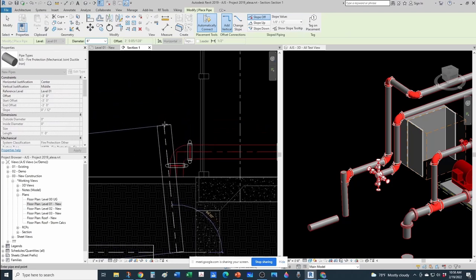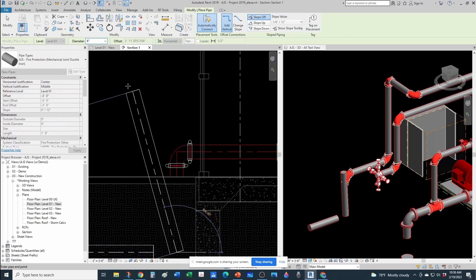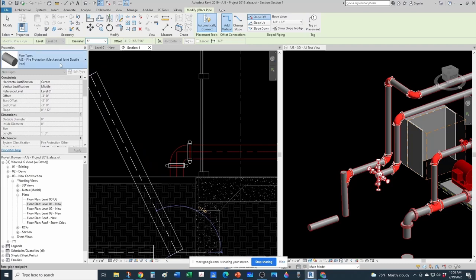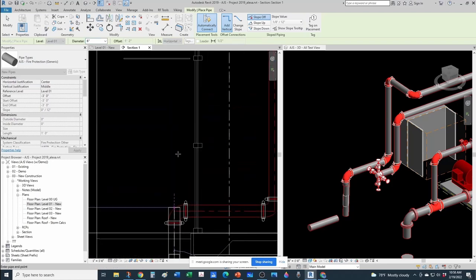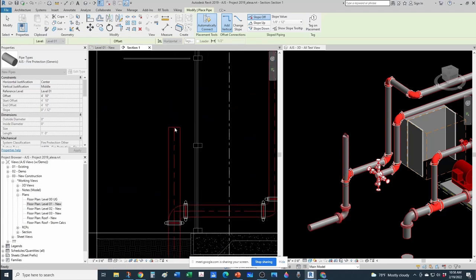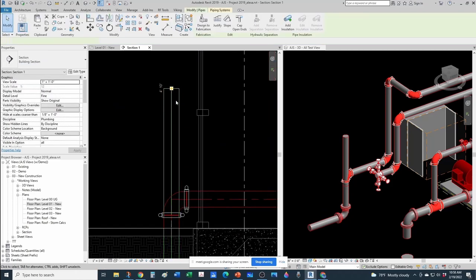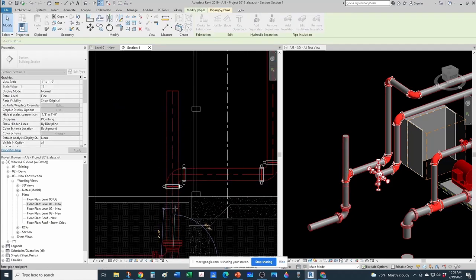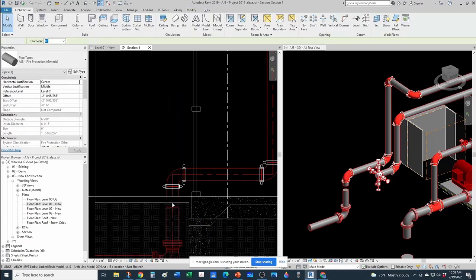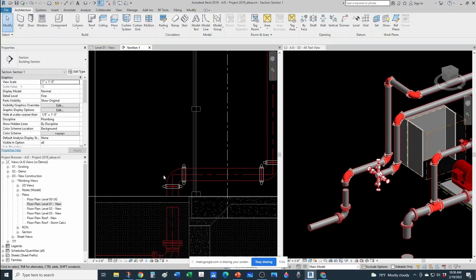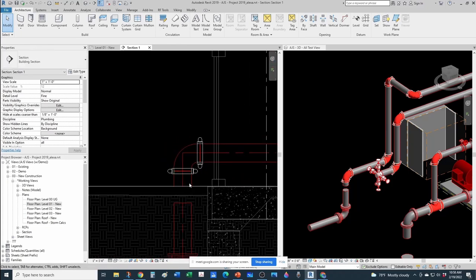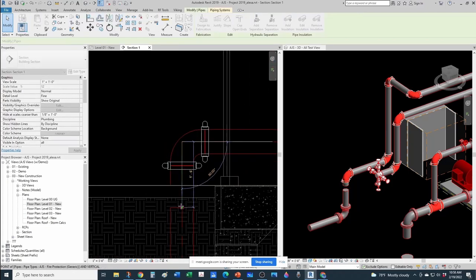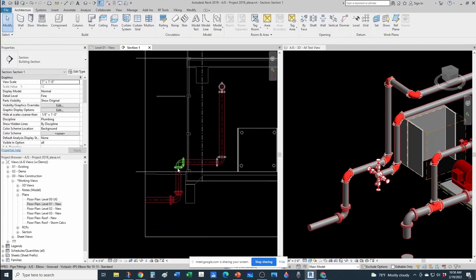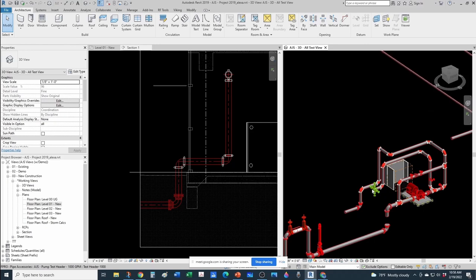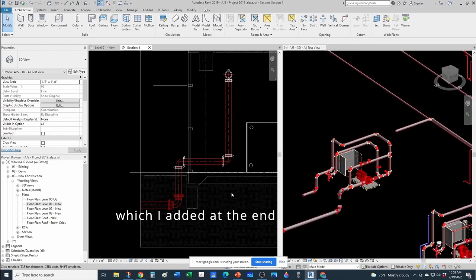And that's what happens when you're doing things live, you know. I cannot hit pause and find out what's happening. A mechanical joint, let's try to change that to our grooved and threaded, and let me just exaggerate it. Yeah, sometimes Revit doesn't understand short distances, so you have to exaggerate at the beginning and then shorten it. It's a little annoying, but you have to get over it and keep going. So now we're connected, and the only thing missing is our jockey pump and jockey pump controller.